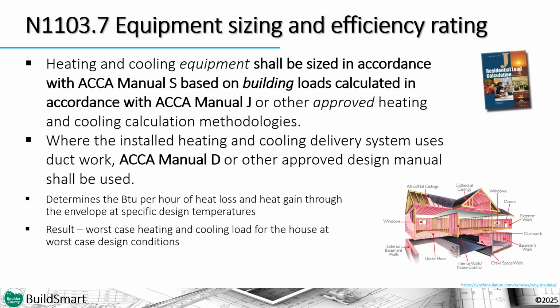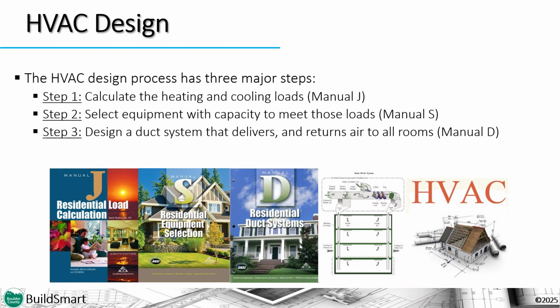Proper HVAC design is also required by the BuildSmart code. A Manual J, S, and D report are required to be turned in for review for permitting of the house. Remember that if specifications change during the construction of the house, these calculations also may need to be updated. The three major steps of HVAC design are first calculating the heating and cooling loads, then selecting the equipment with a capacity that can meet the load, and finally designing a duct system that can distribute and condition air from the equipment to the rooms and then back again. Following these three steps is key to maintaining an efficient, comfortable, and code-compliant home.